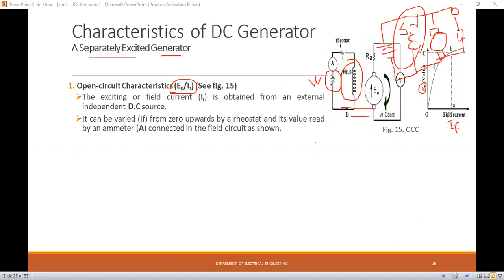To derive the OCC, the generator is run at a constant rated speed — for example, 1500 RPM. The field current IF is increased gradually from zero to its maximum value, step by step, by reducing the resistance of the rheostat. At each step, the values of induced EMF E0 and field current IF are noted down.